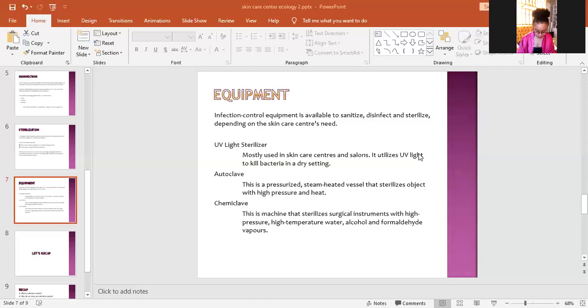So to truly sterilize equipment, an autoclave is used. If you really want to sterilize your equipment, an autoclave has to be used. We said that autoclaves produce high heat and high temperature, so they're very good at sterilizing equipment, and you're sure that they will eliminate bacteria and spore bacteria. An autoclave is a pressurized, steam-heated vessel that sterilizes objects with high pressure and heat, or pressurized steam, preventing microorganisms from surviving. Autoclave is taken from the Greek word auto, meaning self, and Latin clavis, meaning key. This is because the vessel can be self-locking due to pressurization.